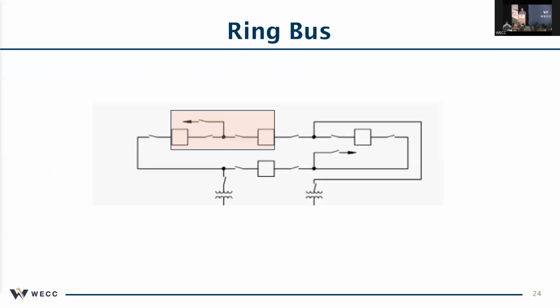Because here we have a ring bus. Same basic story. The shaded area is what the operators are going to consider the boundaries of a facility, and then again extending out with the arrow out to the other bus. That's what they're going to be looking at. It's going to expect it for you to consider in the facility rating.